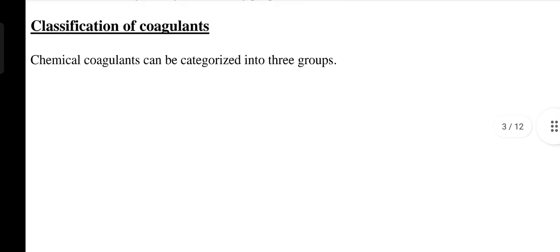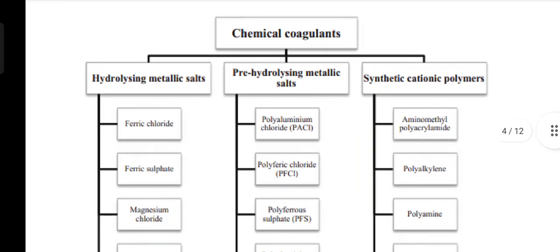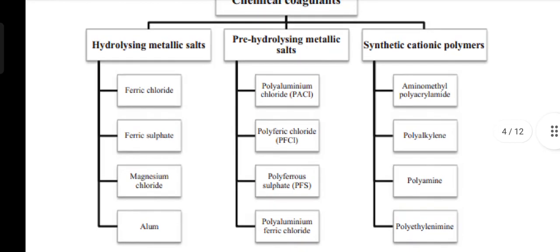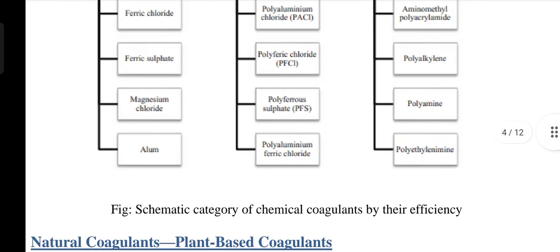Classification of coagulants: chemical coagulants can be categorized into three groups. The first group is hydrolyzing metallic salts, which include ferric chloride, ferric sulfate, magnesium chloride, and alum. The second is pre-hydrolyzing metallic salts, divided into poly-aluminium chloride (PACL), poly-ferric chloride (PFCL), poly-ferrous sulfate (PFS), and poly-aluminium ferric chloride. The last group is synthetic cationic polymers, including aminomethyl polyacrylamide, poly-alkylene, polyamine, and polyethylenimine.